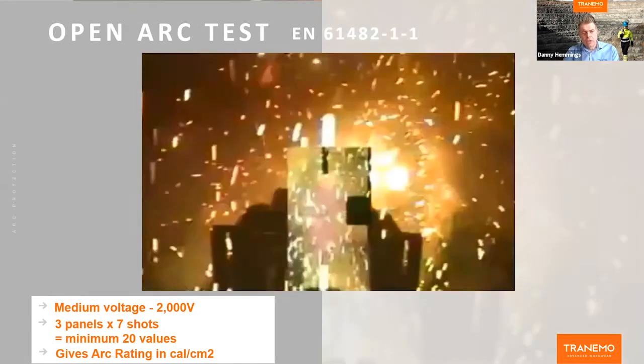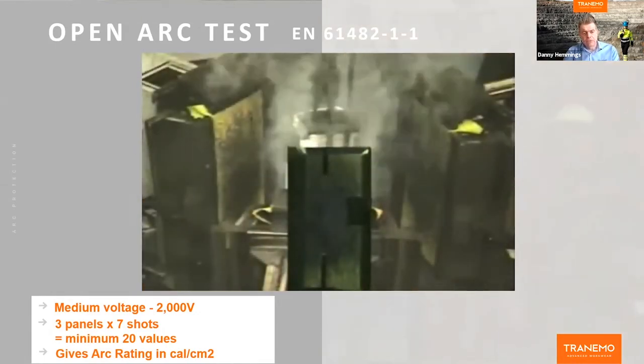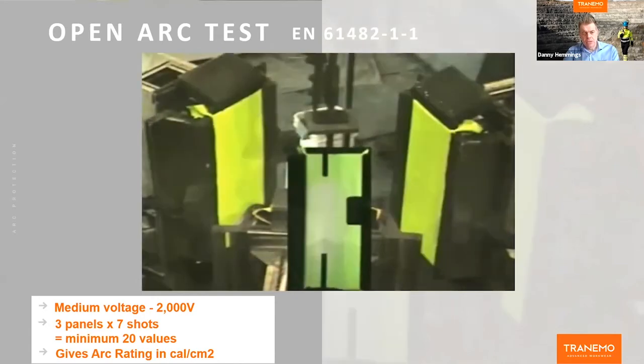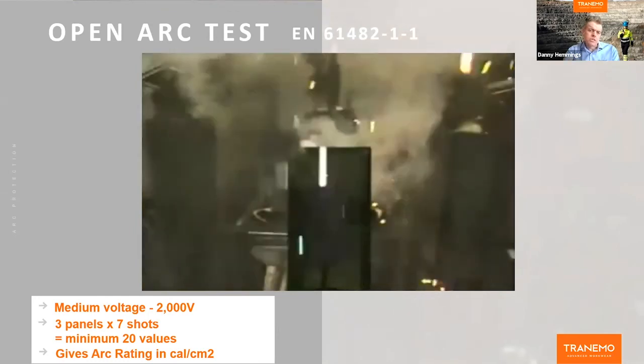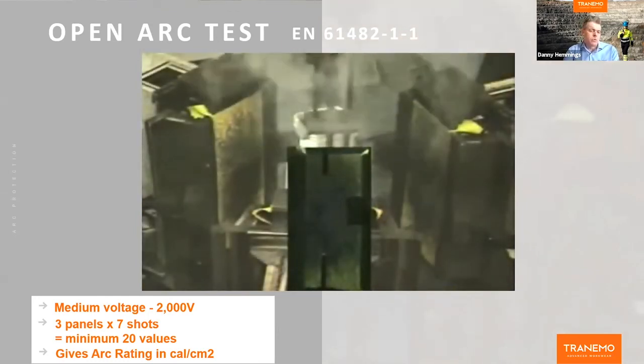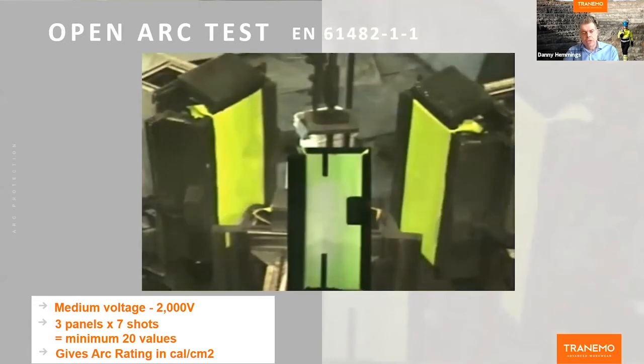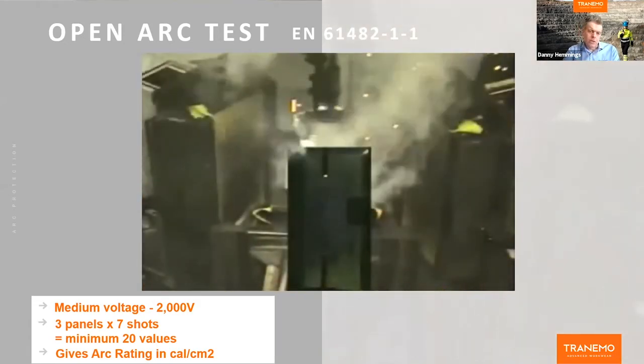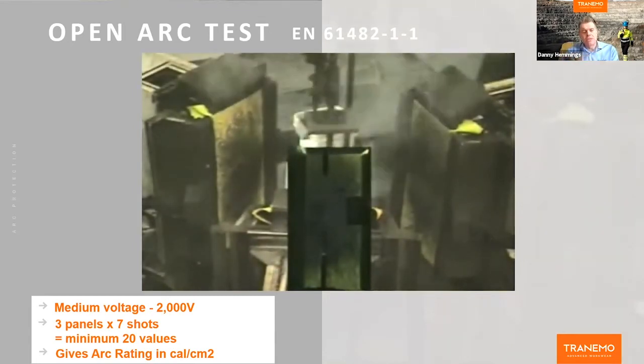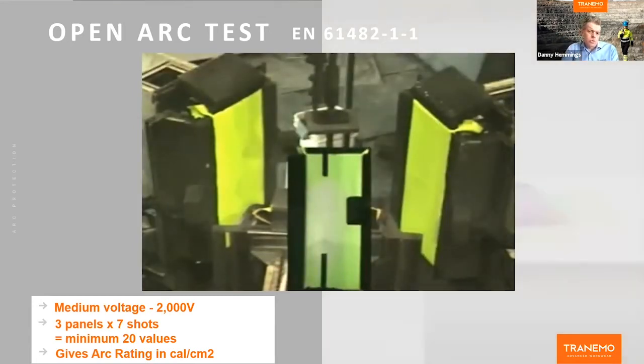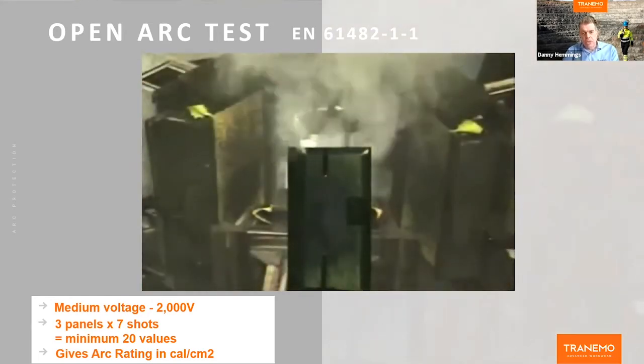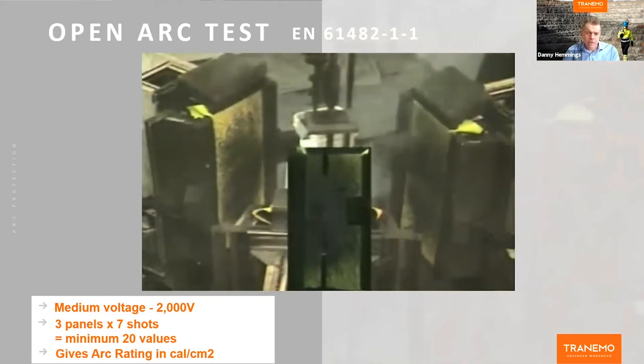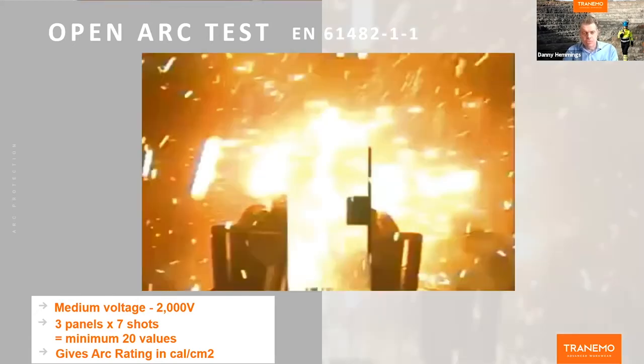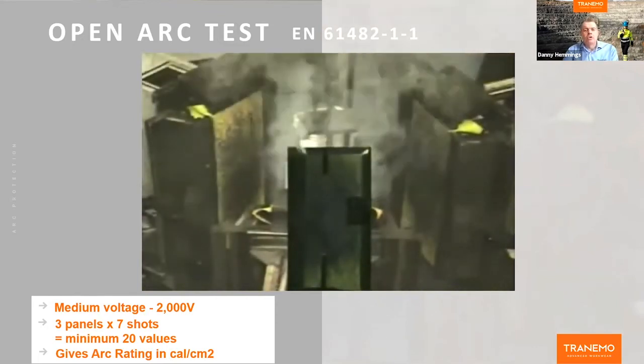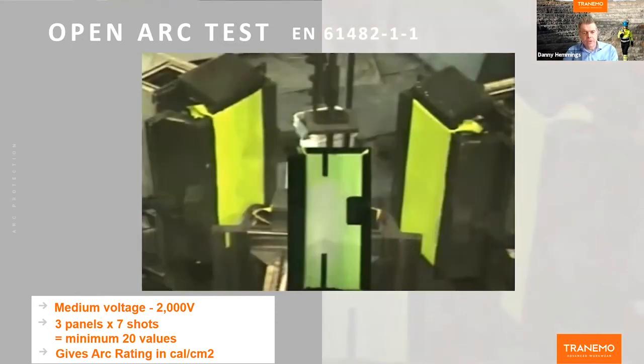If we look by comparison with the open arc method, here we have 3 panels with the fabric inserted onto the panels. There are sensors behind those panels. There are 7 shots that go through that panel. So that gives us, we're looking for a minimum of 20 readable values. They are then plotted into a graph, and that will give us this arc rating for a fabric based in calories per centimeter squared. So you can see there, just from the visual representation of the 2 different test methods, how they differ and how the open arc test results will give a much more rounded and a much more analytical format for protection values.